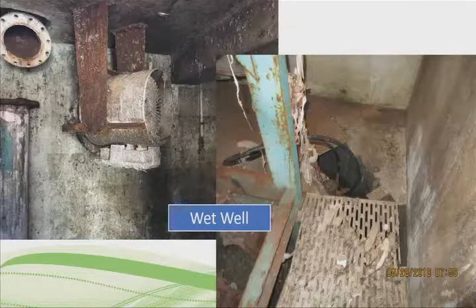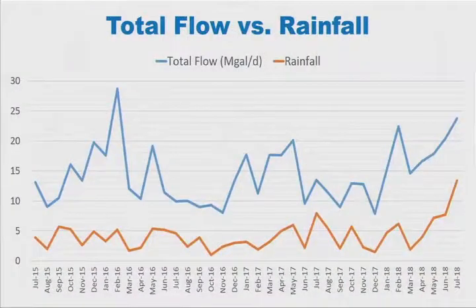Well, that's the Muffin Monster in there. On the right, you can see the hoses going down to it. That's a hydraulic pump on it. It's only as good if the water level stays at the cutters, which you can just barely see the top of down in there, and the cutters are about that big. And it regularly goes up to the old heater there. Fun, fun, fun.